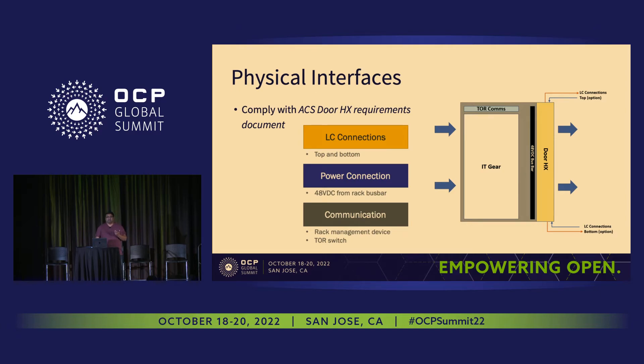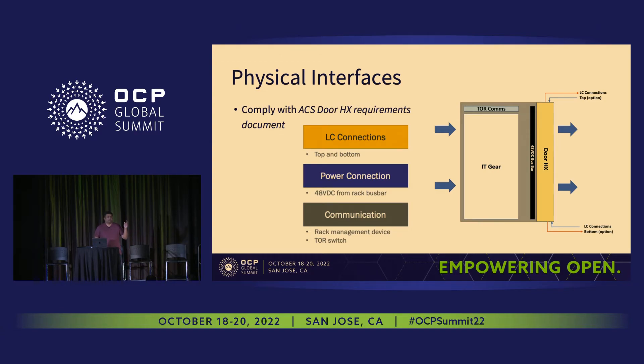Finally, we have communication. You're investing in liquid cooling your rack full of expensive IT gear, and you obviously want to monitor it through its operation. So it's important to define communication interfaces — whether your door heat exchanger talks to a rack management device already being contributed through OCP, or goes straight to the top-of-rack switch and upstreams operational information such as temperatures, fan speeds, or anything required to keep an eye on the operation of the solution.